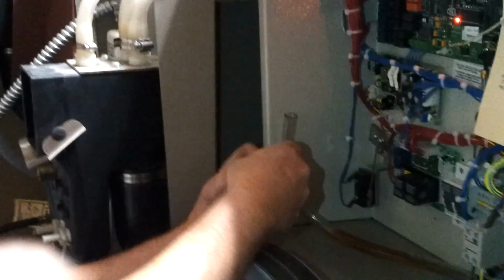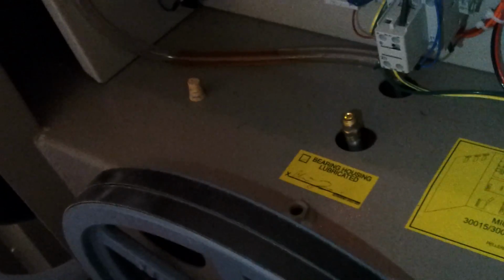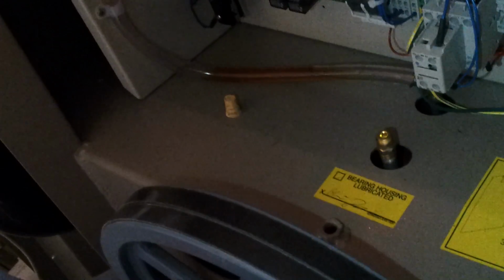So like I was saying, based on an 8-hour day, you'd want to change it 3 times a year, which will be every 4 months. And the way you would drain this is you remove this plug, this cork right here, and just set it here. And then you take an Allen head screw and remove this plug right here. Once you've removed these 2 plugs, then you unscrew your drain plug here and you drain your oil into a small container.